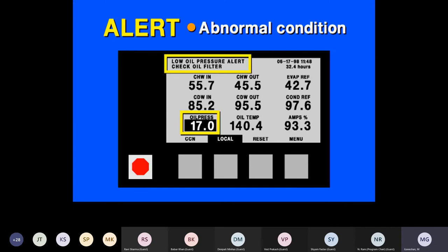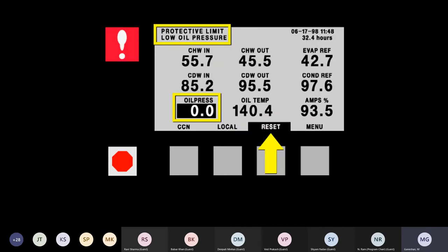Modern chillers and machines are completely microprocessor driven nowadays, so they do not wait. They always tell you first and give an alert. If you do not take corrective action on the alert, it will go to alarm next, and it will not wait for us. Even then, if you just reset it and keep starting it, any compressor will fail, there is no doubt about it. If there is an indication, we need to find out why it has failed and why it is tripping, find the cause, and then take corrective and preventive action. Otherwise, if you restart it immediately, nothing can prevent it from failing.